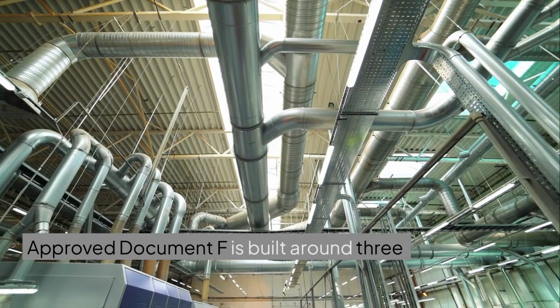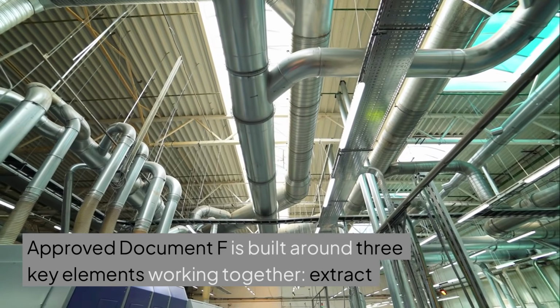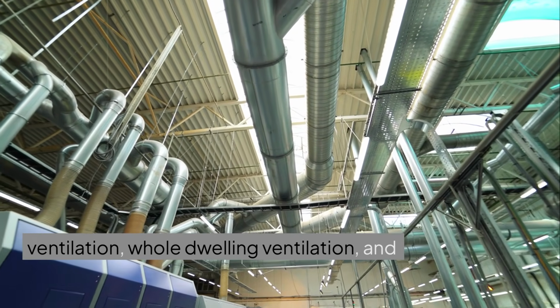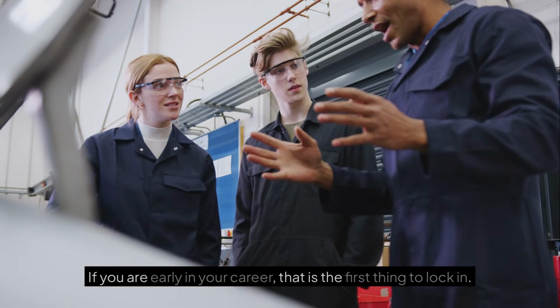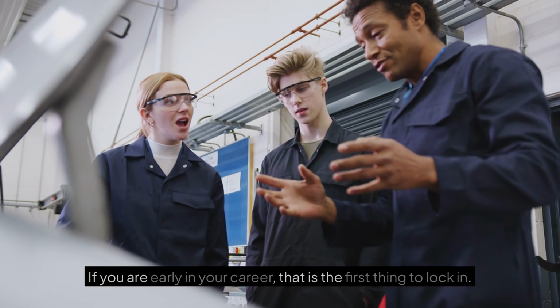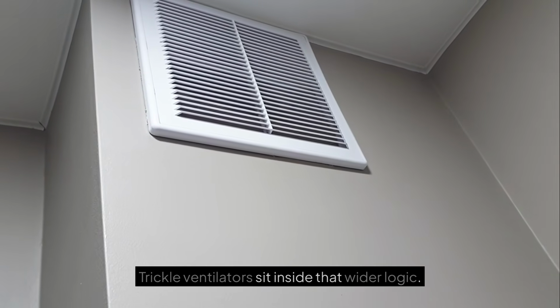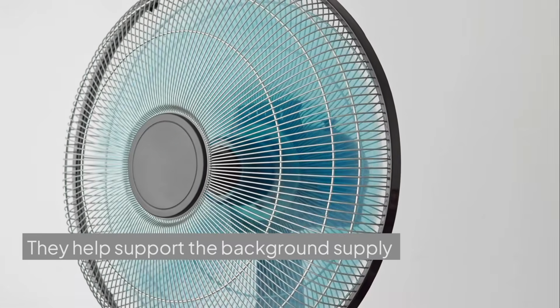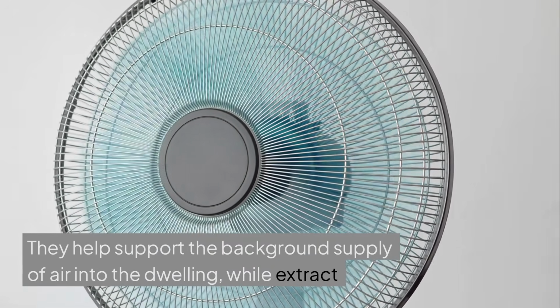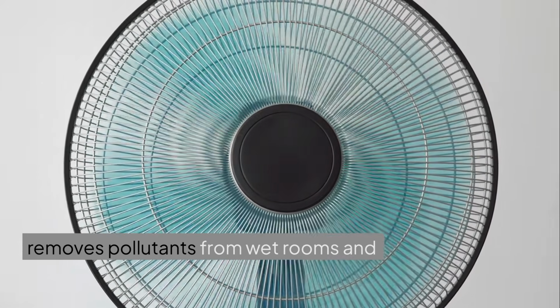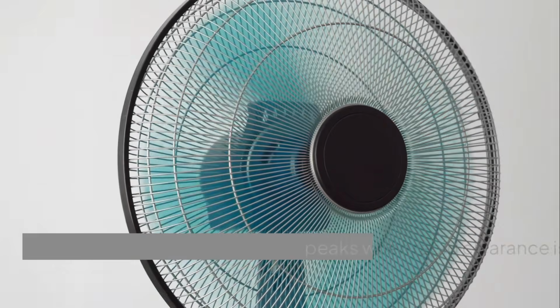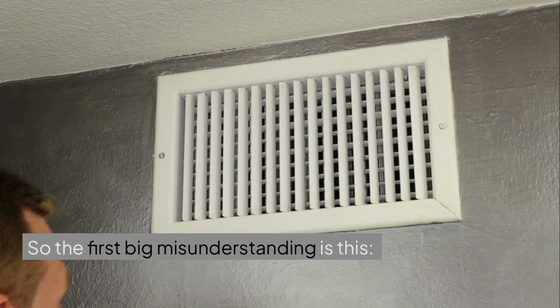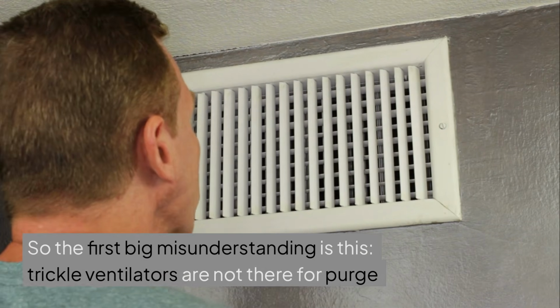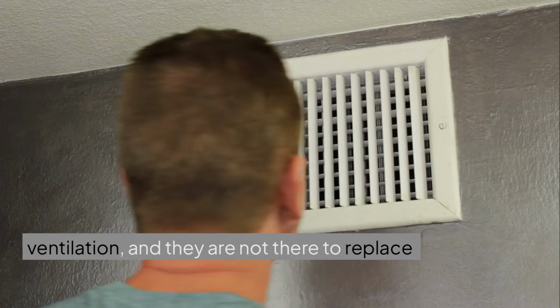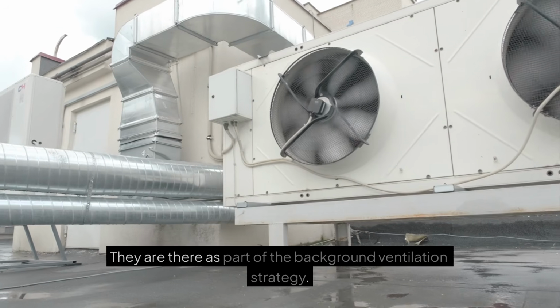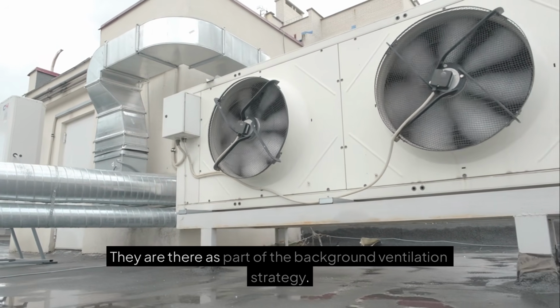Approved Document F is built around three key elements working together: extract ventilation, whole dwelling ventilation, and purge ventilation. If you are early in your career, that is the first thing to lock in. Trickle ventilators sit inside that wider logic. They help support the background supply of air into the dwelling, while extract removes pollutants from wet rooms and purge ventilation deals with short-term peaks when rapid clearance is needed. So the first big misunderstanding is this: trickle ventilators are not there for purge ventilation, and they are not there to replace extract. They are there as part of the background ventilation strategy.